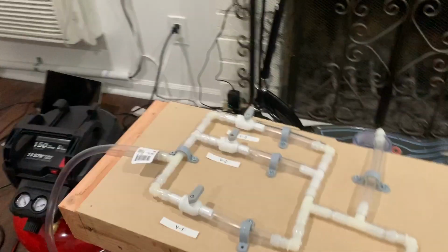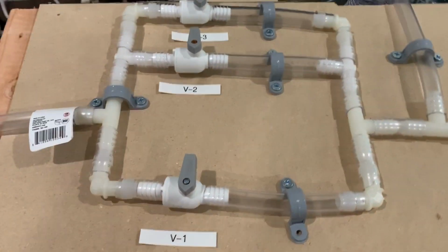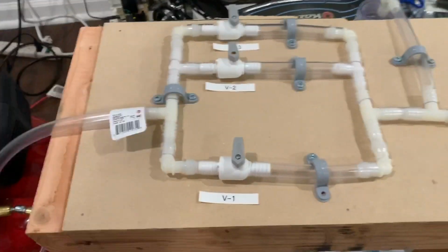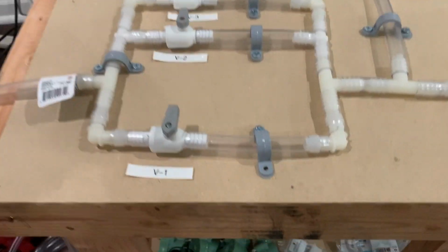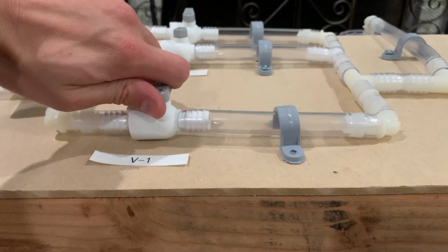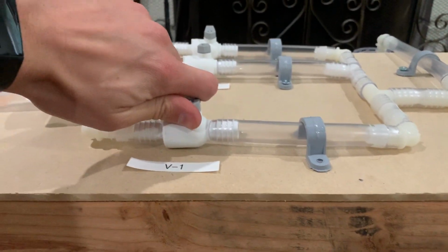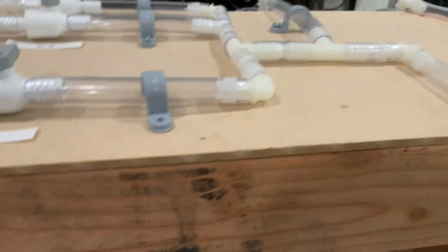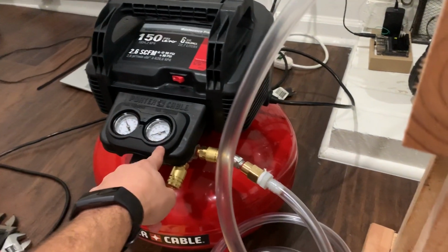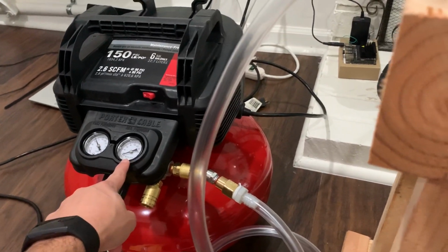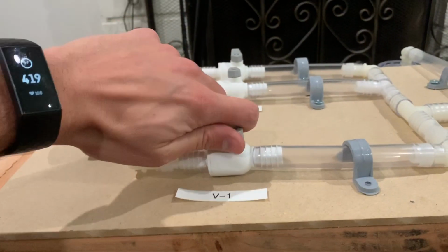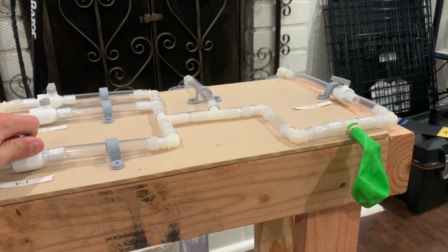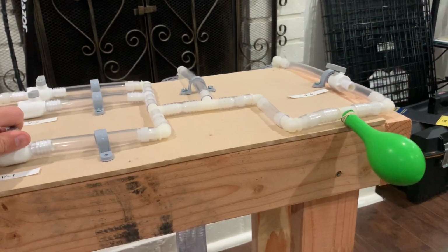So it's important to note right now we don't have the orifices installed, so we are not able to control the flow rate super accurately, other than by me personally throttling one of these valves, only opening it a small amount. If I do that, then that will open up this entire inspiratory phase up to the balloon to potentially up to the 10 psi that we had on our gauge here, just below 10 psi. So you can see that if I start to open this valve, a few things will happen. One is the balloon will start to inflate.